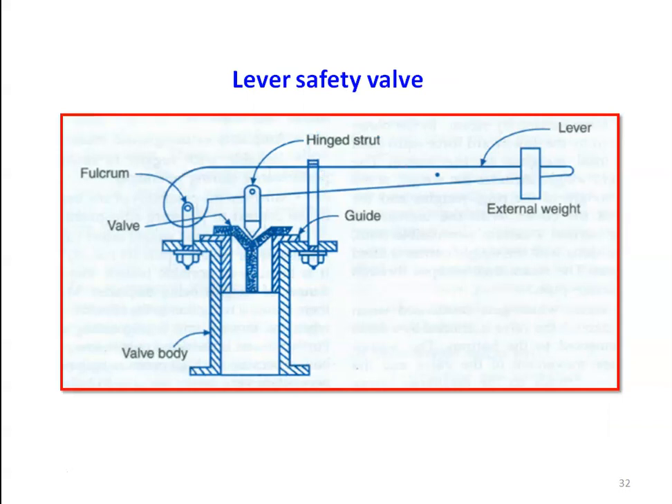This is the lever safety valve. The working principle is the same — we have an external weight, and depending on the position of the external weight there will be force acting on the valve. We have a Y-type valve arrangement with a guide, a fulcrum, a hinged strut, and a valve body attached to the boiler drum. Steam pressure acts on the bottom of the valve, and by adjusting the external weight via the lever mechanism we retain the valve in the seat. By repositioning the weight we can adjust the set pressure. This is called the lever safety valve.